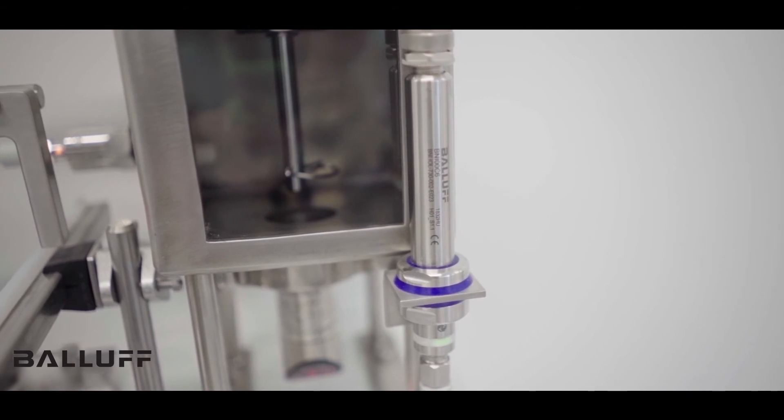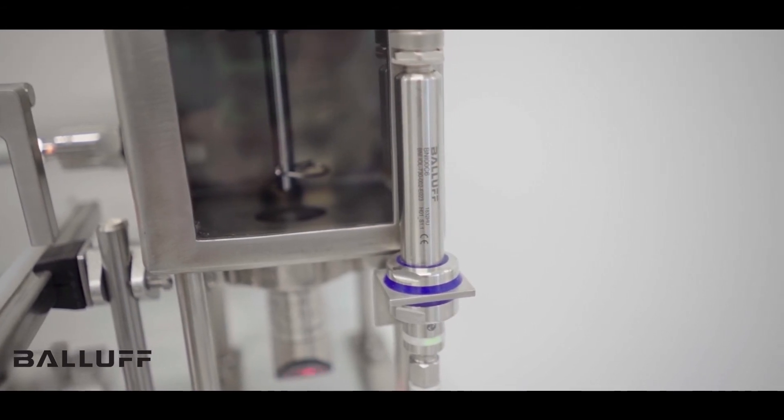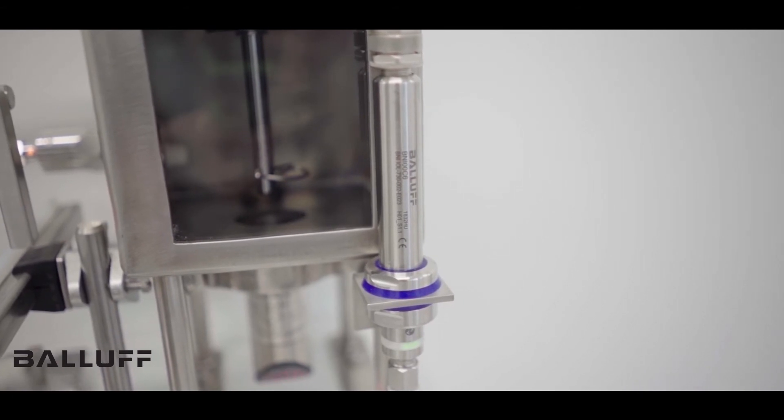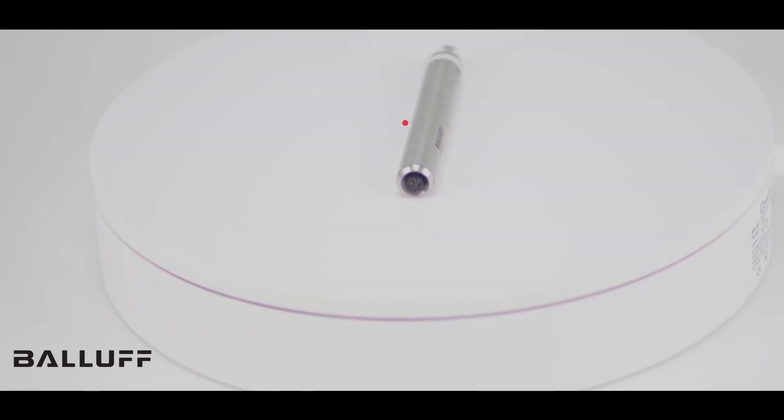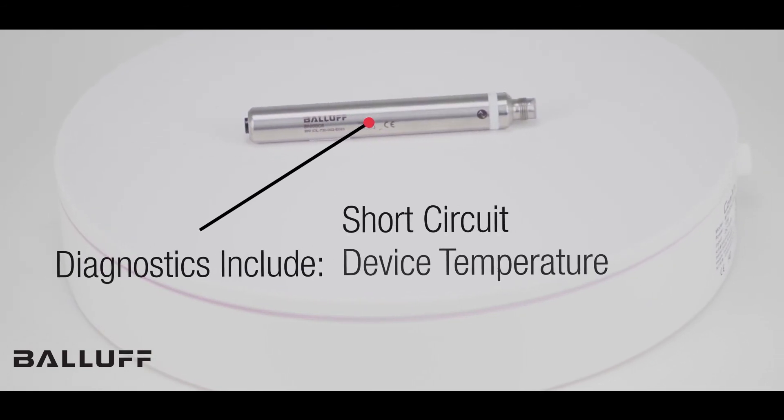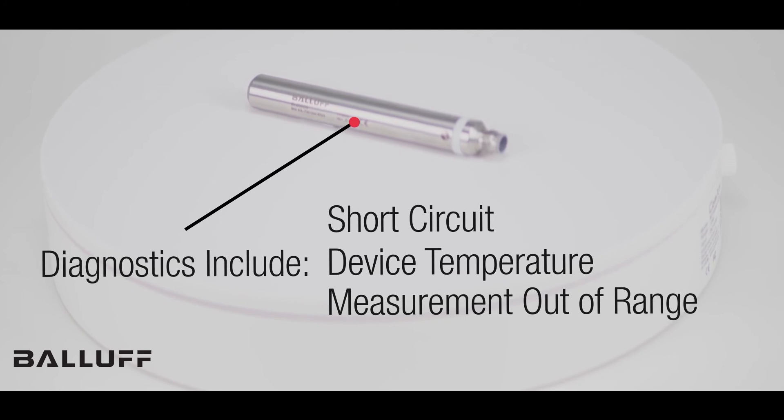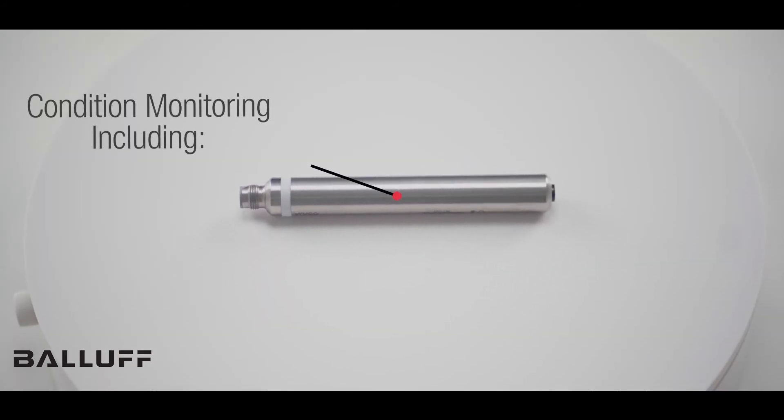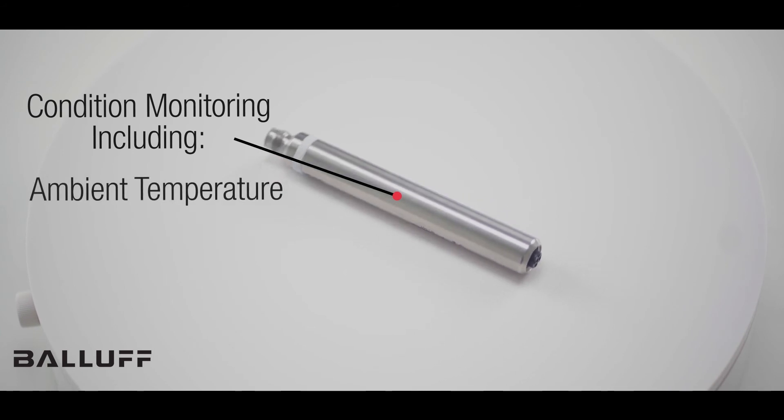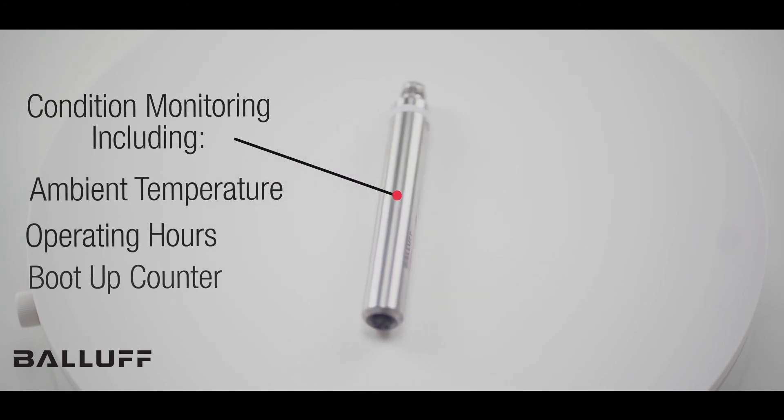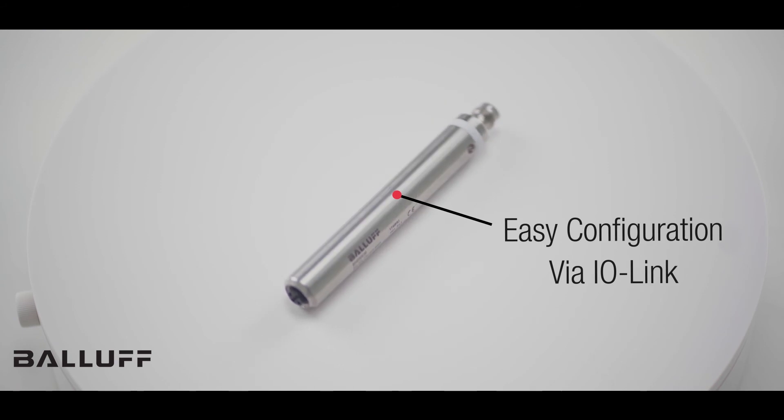In addition to the cost savings from eliminating the need for analog in-chassis interface boards or network adapters and reduced shielded cable runs, these solutions offer diagnostics which include short circuit, device temperature, measurement out of range, and even thermocouple wire breaks, condition monitoring data including ambient temperature, operating hours, and boot-up counter, and easy configuration via the IO-Link interface.